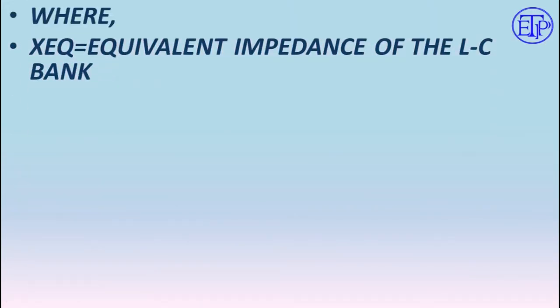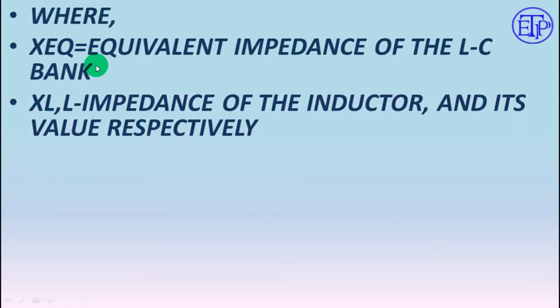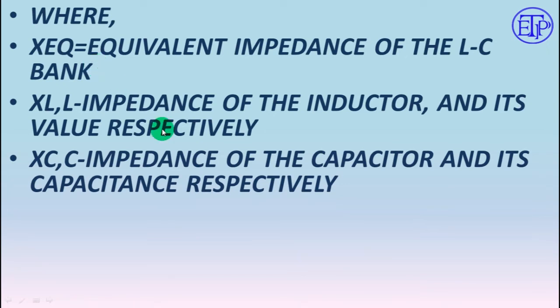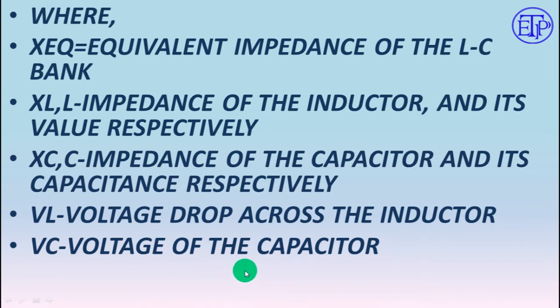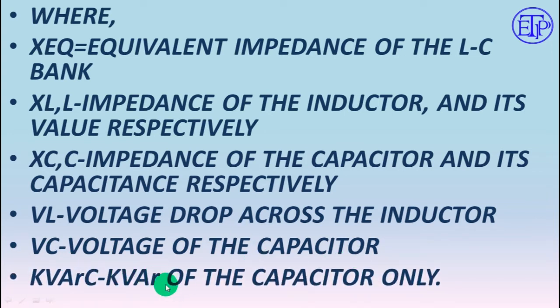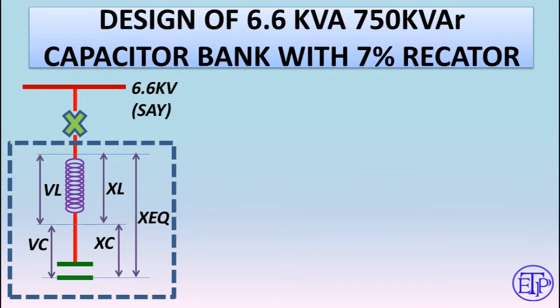The following terminologies will be used: XEQ stands for equivalent impedance of the LC bank; XL and L stand for the reactance and inductance in Henry of the inductor; XC and C stand for the impedance and capacitance of the capacitor; VL means voltage drop across the inductor; VC means voltage of the capacitor. KVAR refers to the KVAR of the capacitor only — not the entire bank. The bank KVAR is 750 KVAR, but this is only the KVAR of the capacitor itself.